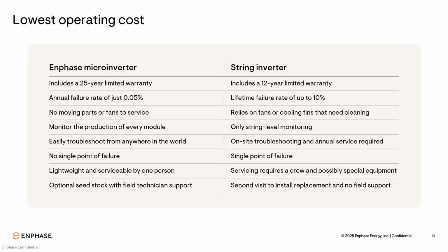And we can stack it up side by side against a string inverter and see. We have a longer warranty, 25-year. Our failure rate is 0.05% compared to potentially up to 10%. This is a huge one for O&M contracts and O&M servicing. We have no moving parts or fans that require annual servicing. Most large string inverters require cleaning of cooling fins or fans that need to be serviced on an annual basis.